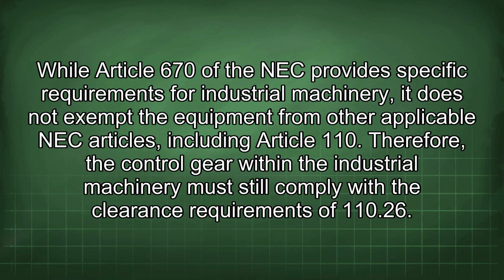While Article 670 of the NEC provides specific requirements for industrial machinery, it does not exempt the equipment from other applicable NEC articles, including Article 110. Therefore, the control gear within the industrial machinery must still comply with the clearance requirements of 110.26.